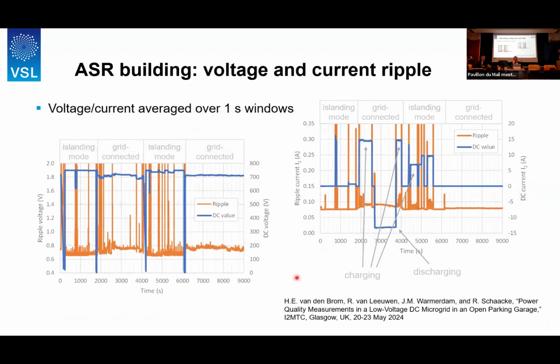Some time-dependent measurements. This is simply the voltage and the current average over 1 second windows. So the DC current and voltage, and also the ripple. So in both of these pictures, this is the voltage and this is the current. You see on the right-hand axis the DC component, and on the left-hand axis you see the ripple voltage. And so here the blue is the voltage, and the orange is the ripple. And you can see here we were in islanding mode, grid connected mode, islanding mode again, and grid connected mode.